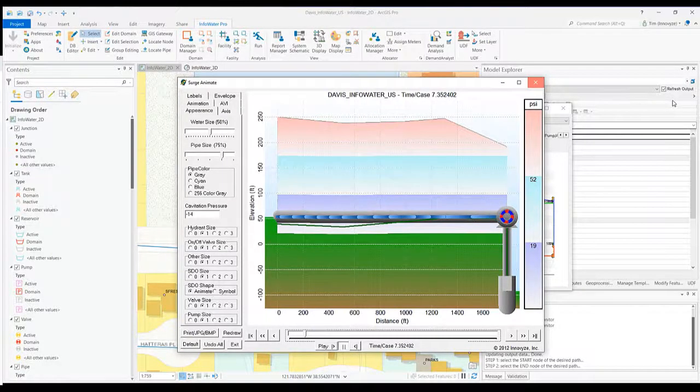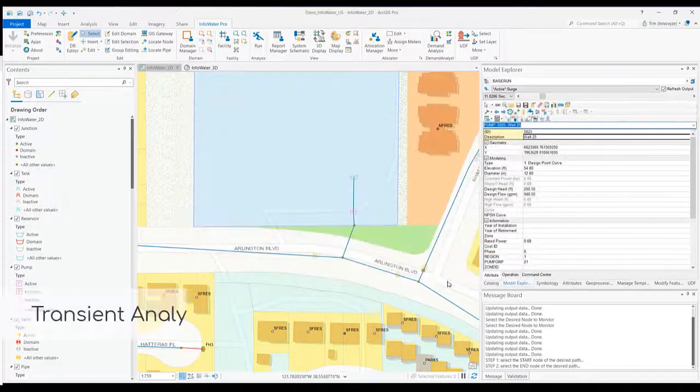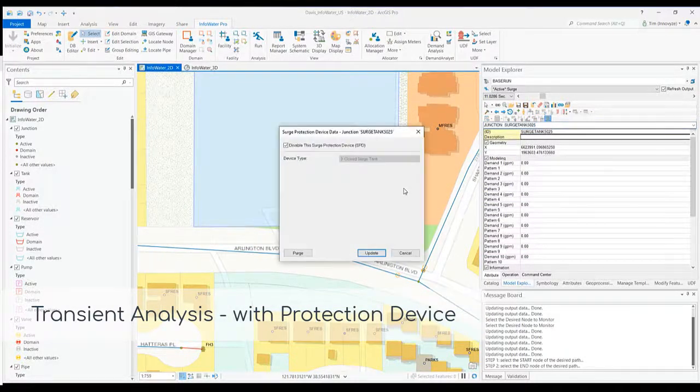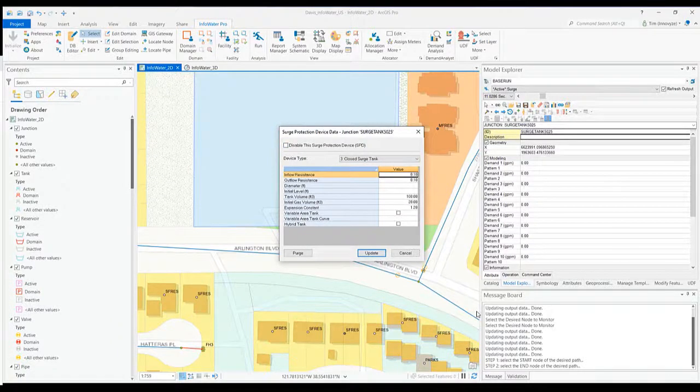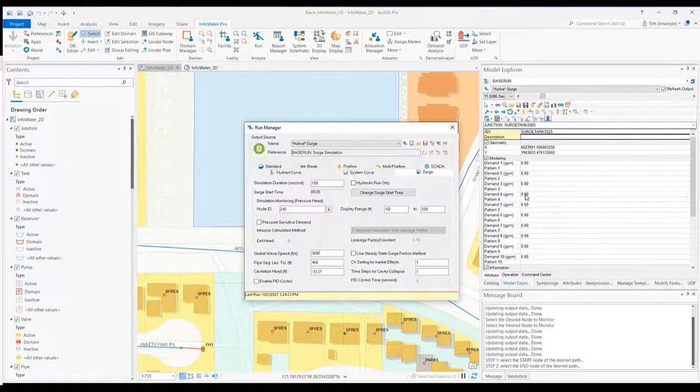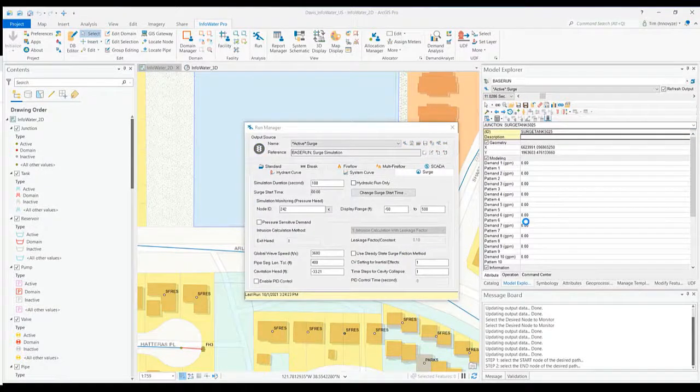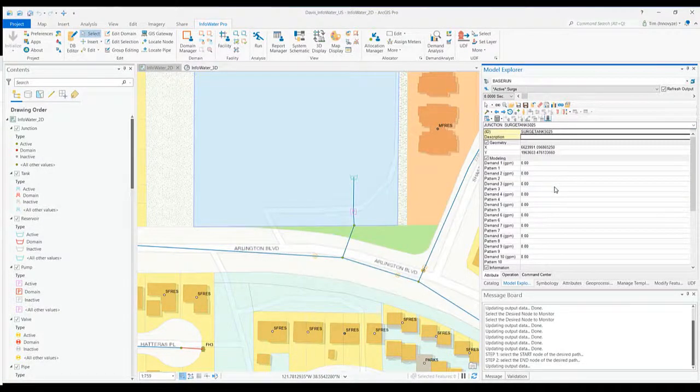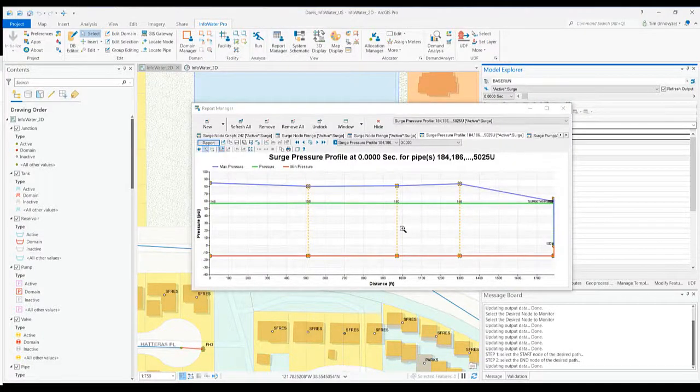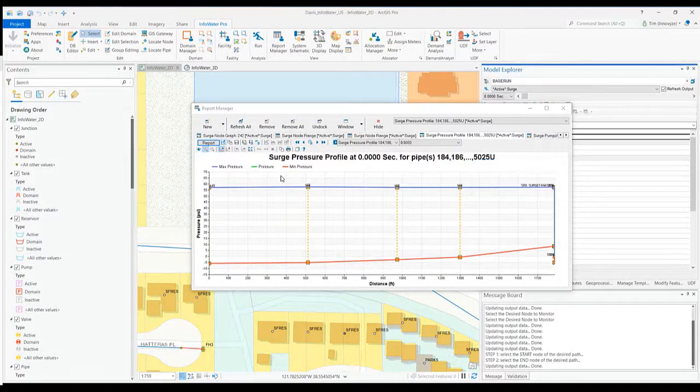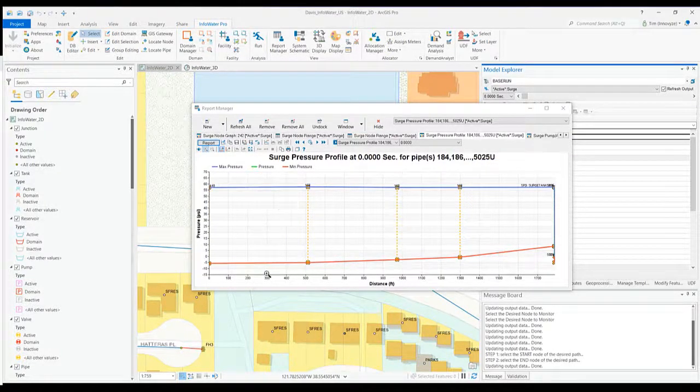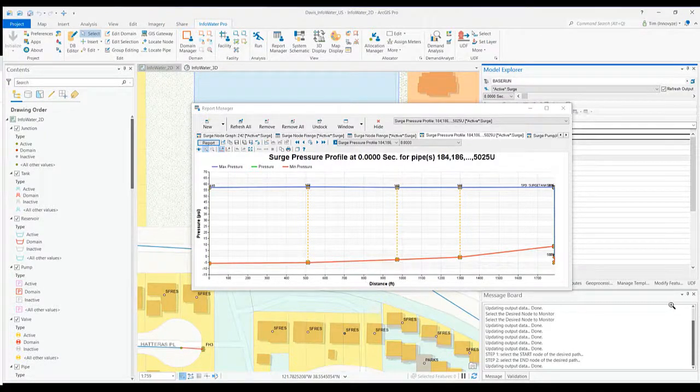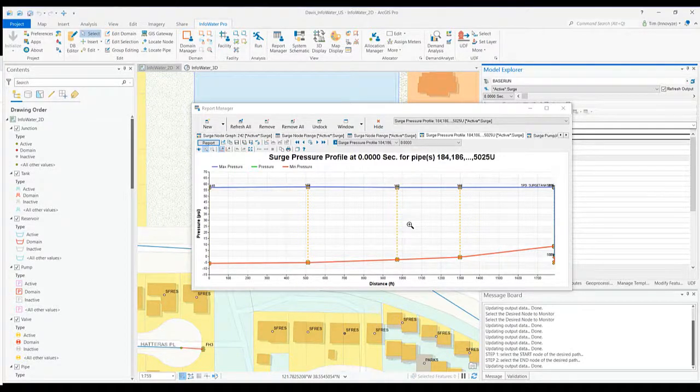Compare that to if I close this out and add that surge tank here with particular parameters, update that, and rerun this analysis. It just takes a few seconds. Then go back to my report manager, refresh that graph now that I've added that surge device. A little bit better, not quite as high, not quite as low. Still definitely a surge event there, so I might have to go back and change the parameters for that surge tank, but a lot less significant.